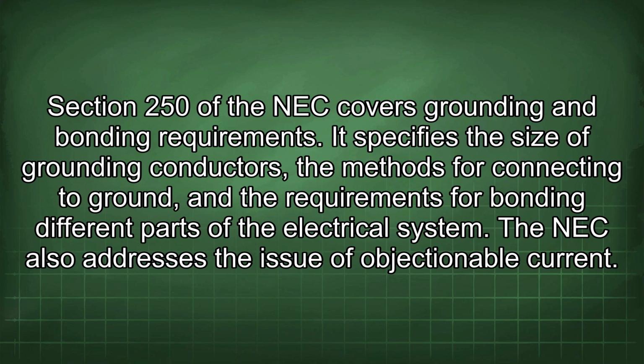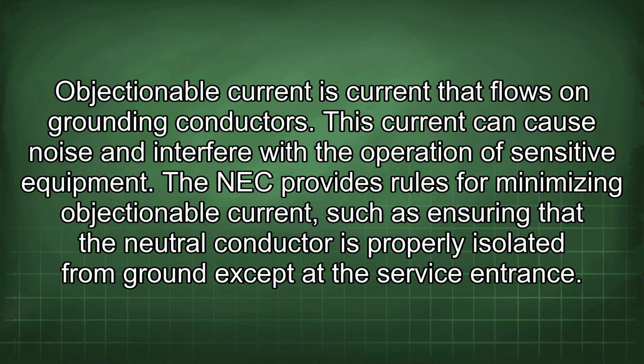Section 250 of the NEC covers grounding and bonding requirements. It specifies the size of grounding conductors, the methods for connecting to ground, and the requirements for bonding different parts of the electrical system. The NEC also addresses the issue of objectionable current. Objectionable current is current that flows on grounding conductors. This current can cause noise and interfere with the operation of sensitive equipment. The NEC provides rules for minimizing objectionable current, such as ensuring that the neutral conductor is properly isolated from ground except at the service entrance.